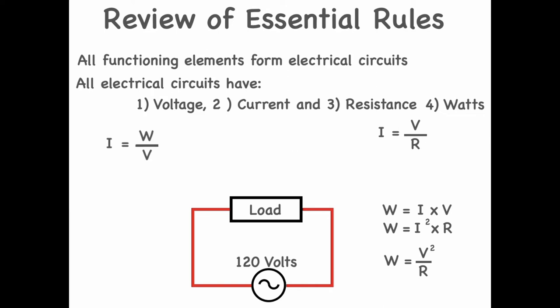Now if the load were not a 100 watt incandescent light bulb, but a 1 kilowatt heater, then the connected current is 1000 divided by 120, or 8.33 amps. Keeping the load of a 1 kilowatt heater and changing the connected voltage to 240 volts, then the connected current is 1000 divided by 240, dropping the current to 4.17 amps. At first glance, this might seem contradictive, in that we double the voltage, and you would think that we would double the current. However, the 1000 watt heater would have to be rated at 240 volts. That is to say, that the load will consume 1000 watts when connected to 240 volts. Therefore, the connected current is given by the rated power, 1000 divided by the rated voltage, 240.